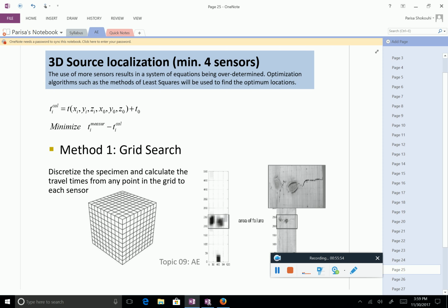I agree. We place the transducers based on the guidelines that we talked about. Coverage, depending on the application, what you want to do with your data. You know exactly where they are, just like the two on the right. You don't touch them. Actually, one thing about coupling is that you have to make sure that your transducers are not moving, because that would be a nightmare. So once you have that, you have recorded a lot of things, right?